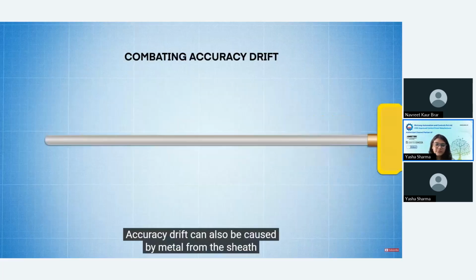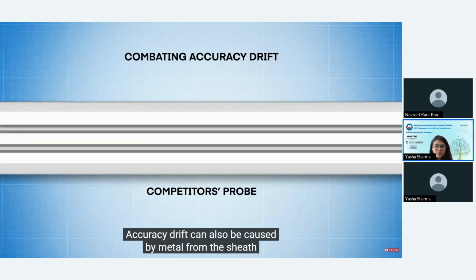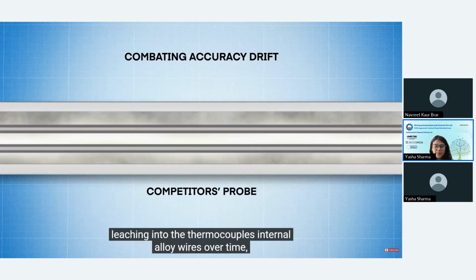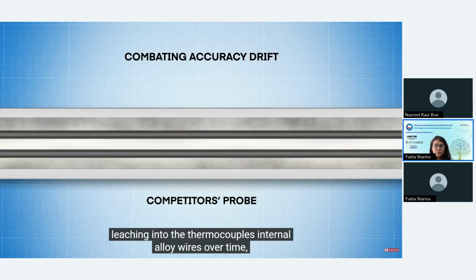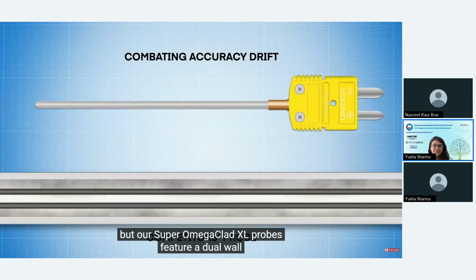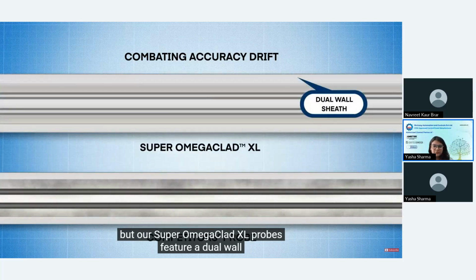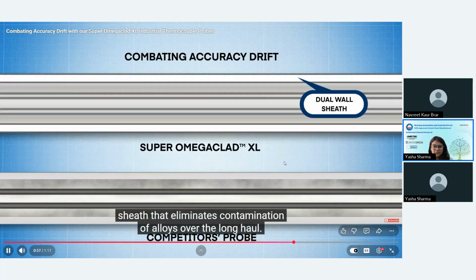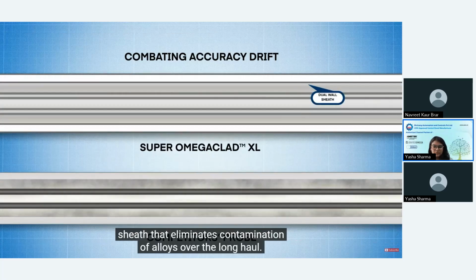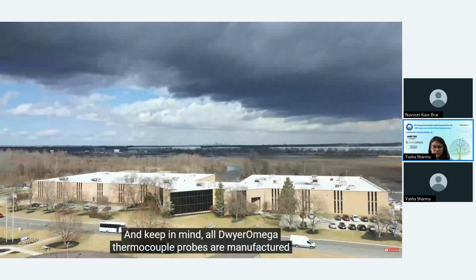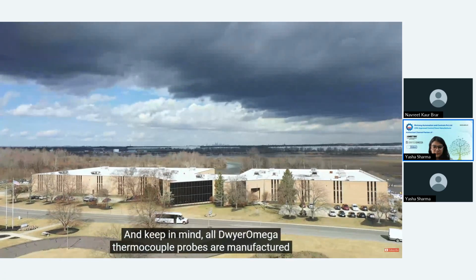Accuracy drift can also be caused by metal from the sheath leaching into the thermocouple's internal alloy wires over time. Our Super Omega Clad XL probes feature a dual wall sheath that eliminates contamination of alloys. And keep in mind, all Dwyer Omega thermocouple probes are manufactured in-house at our assembly plant.